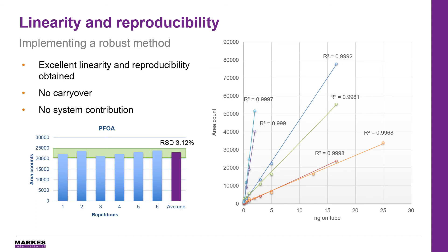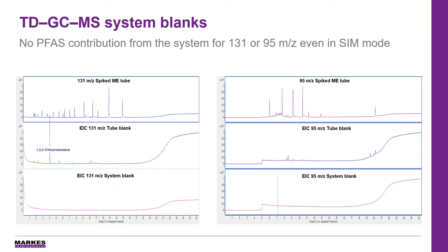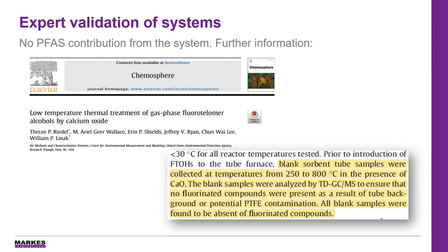The next steps of validating a method are to evaluate the linearity, reproducibility and repeatability, which you can see in the graphs on this slide, and they're well within the desired range. In addition, no carryover was observed for any of the tested PFAS compounds and, importantly, no system contribution was detected. In analytical methods for the measurement of PFAS in water, concerns have been raised about inherent instrument contribution of PFAS compounds and certain materials have been highlighted as possible areas of concern. With that in mind we carried out extensive studies to ensure no background contribution was seen, and that has also been verified by the leading experts in PFAS analysis at the US EPA.